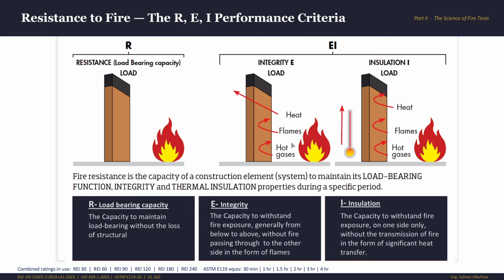And then you can see some certificates with an E only, the integrity. That means the element is too thin to block the heat. There is no insulation. Think of a fire-rated glass door. It can stop the flame, but not the heat. Stand near it and you can still feel the heat radiating from it. The unexposed side is getting really hot, but it has some integrity.